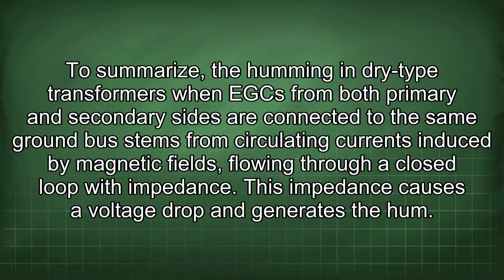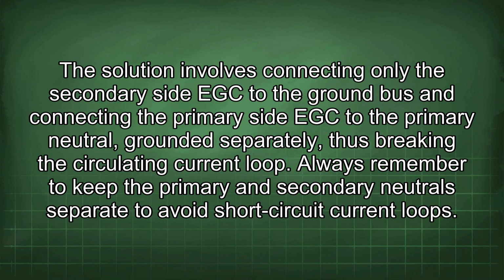To summarize, the humming in dry-type transformers when EGCs from both primary and secondary sides are connected to the same ground bus stems from circulating currents induced by magnetic fields flowing through a closed loop with impedance. This impedance causes a voltage drop and generates the hum. The solution involves connecting only the secondary side EGC to the ground bus and connecting the primary side EGC to the primary neutral, grounded separately, thus breaking the circulating current loop. Always remember to keep the primary and secondary neutrals separate to avoid short-circuit current loops.